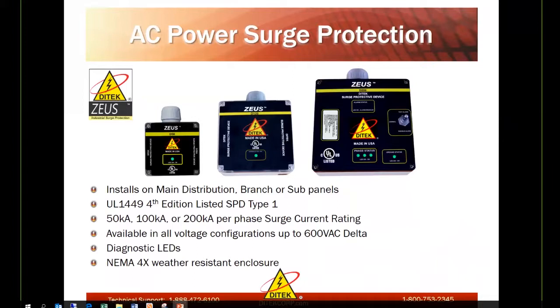They're all NEMA 4X weather resistant with LED. The D200 comes not with just 1 LED, but 3, 1 for each phase, with a ground status indicator, dry contacts, and audible alarm. On the D50 and D100, it's a single LED, but it references all legs. So if you lose a phase, the light goes out. Time to replace.